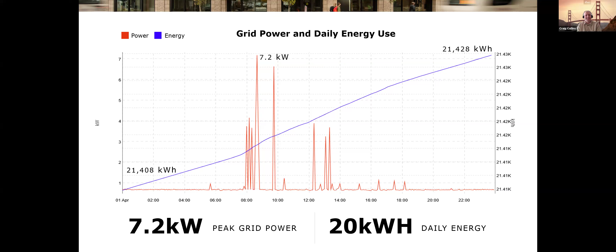Peak power of the UPS is 7.2 kW, which I think would be quite reduced from what the native elevator power demand is. So one of the other benefits of the UPS system is that you're smoothing out the grid power that would otherwise be used for the elevator. It helps to reduce the peaks, which might be beneficial for your utility and maybe for your utility bills. You can also see that we do get some use right around the start of the day. I think this was a work day, with a little bit of use around lunchtime. And then when people are filing out, they tend to take the stairs down, and some people, myself included, tend to take the elevator back up. So, next slide.